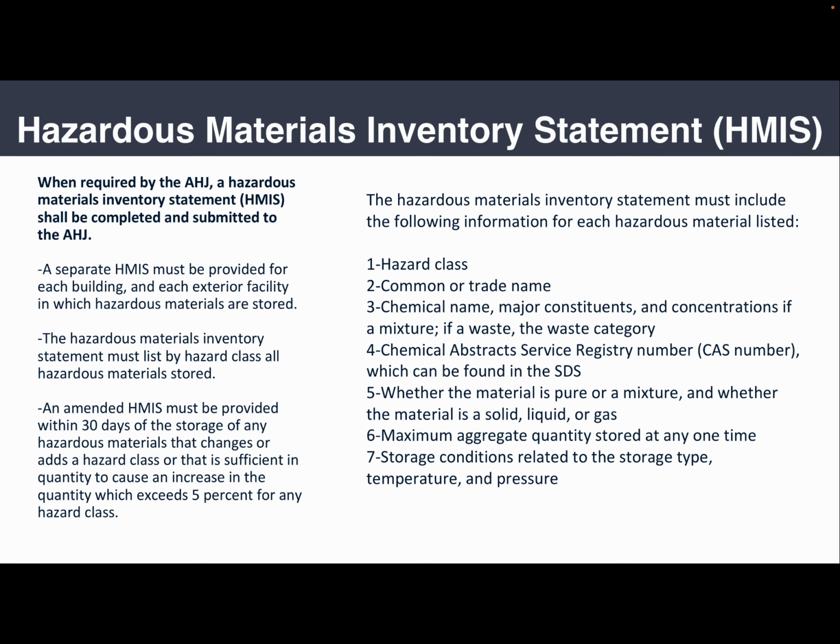And an updated HMIS must be submitted within 30 days. An amended HMIS must be provided within 30 days of the storage of any hazmat that changes or adds a hazard class, or that is sufficient in quantity to cause an increase which exceeds 5% for any hazard class.